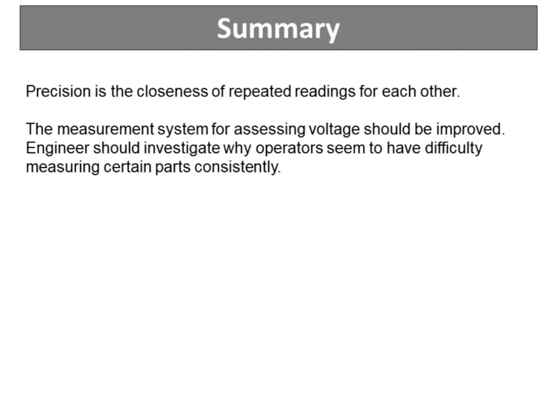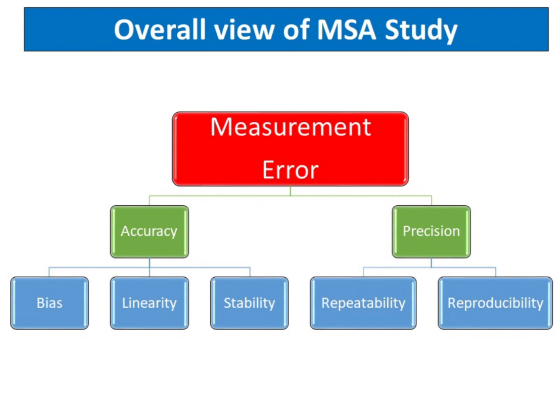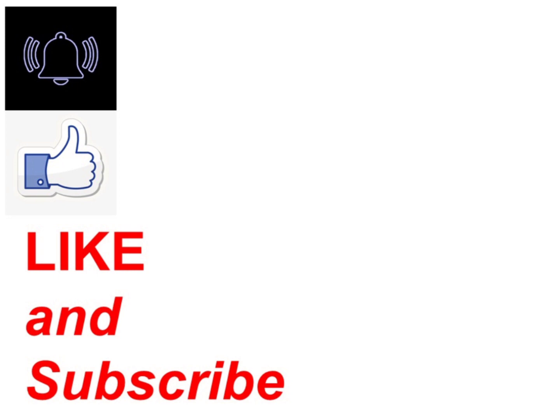In summary, precision is the closeness of repeated readings for each other. The measurement system for assessing voltage should be improved. Engineers should investigate why operators seem to have difficulty measuring certain parts consistently. MSA assesses whether the gauge is capable in terms of precision and accuracy. The accuracy of a measurement system has three components: bias, linearity, and stability. Precision, or measurement variation, has two components: repeatability and reproducibility. Thanks for watching. Remember to subscribe to my channel. Bye, see you next time.